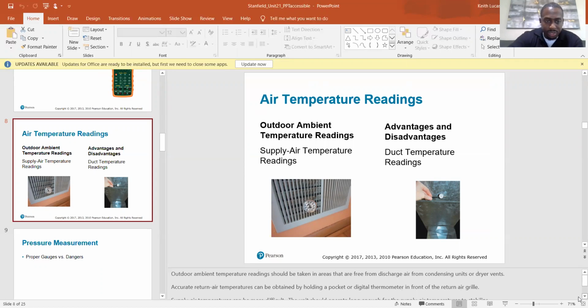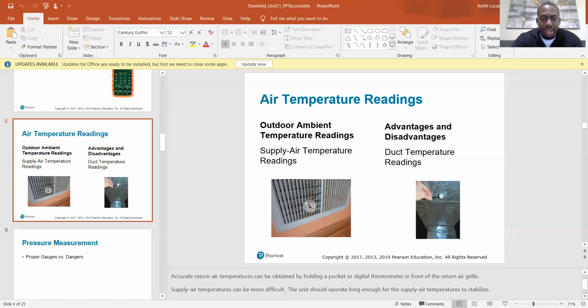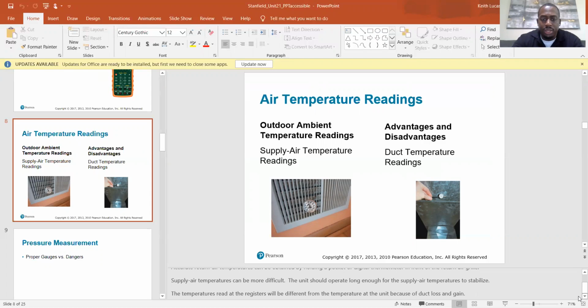But anyway, so outdoor ambient temperature readings should be taken in areas that are free from discharge air from cooling units or dryer vents. Accurate return air temperatures can be obtained by holding a pocket or digital thermometer in front of the return grill. Supply air temperatures can be more difficult. The unit should be operating long enough for the supply air temperature to stabilize. The temperatures read at the registers will be different from the temperature at the unit because of duct loss and gain.